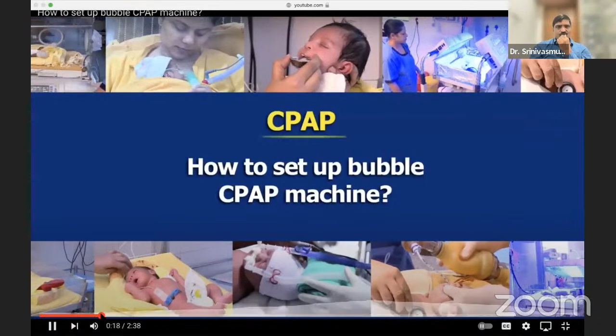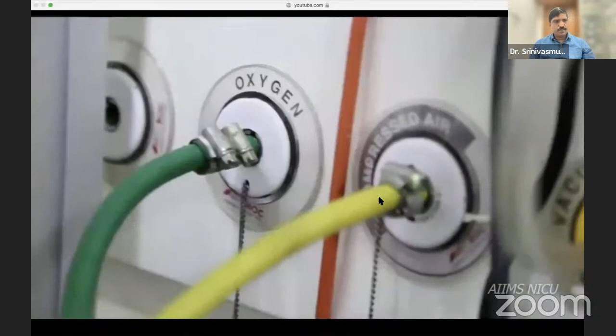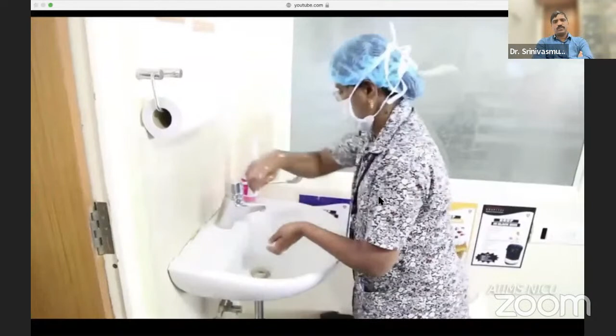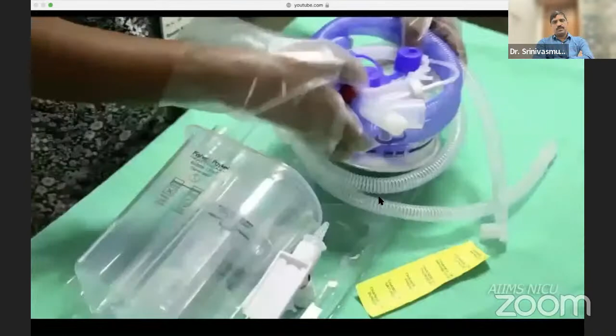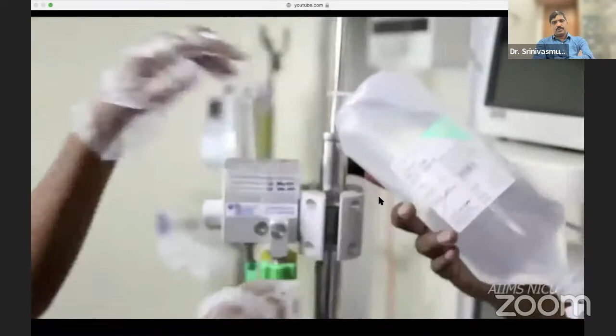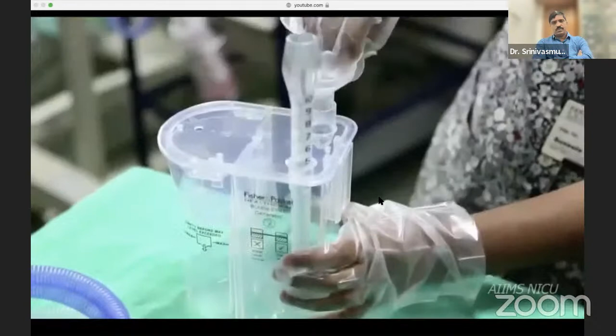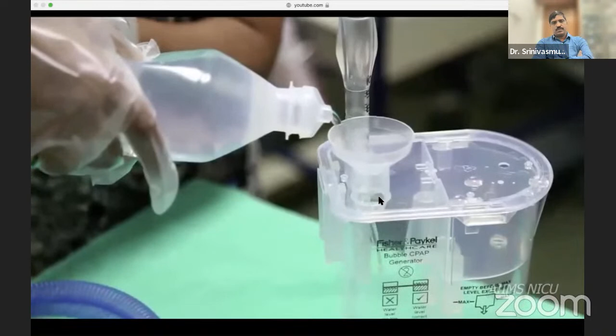Preparation includes assembling the machine, bubble CPAP circuit, a cloth and a disinfectant for cleaning the machine, gloves and distilled water. Clean the machine with 2% Cidex or any other approved disinfectant. Clean the heater wire and temperature probe with a clean and soft cloth and sterilium. Connect the machine to compressed source of air and oxygen. After washing hands and wearing clean gloves, open the disposable CPAP circuit. Fix the water chamber onto the servo humidifier and fill it with distilled water. Use the autofill option of fixing the distilled water bottle to a stand for filling the water chamber.